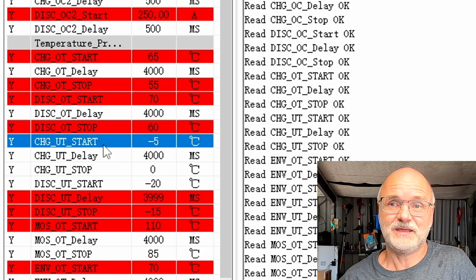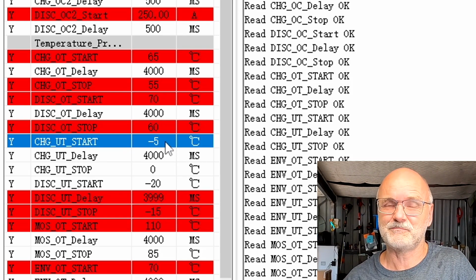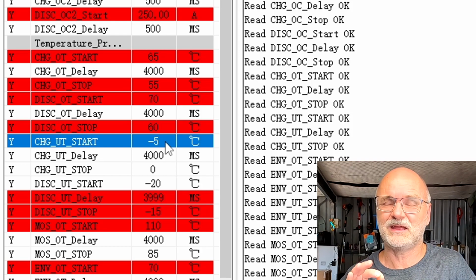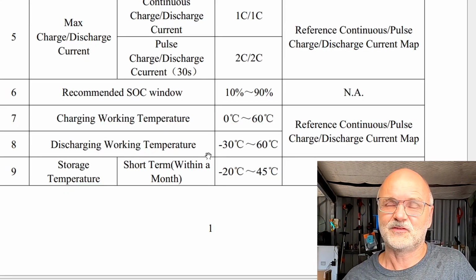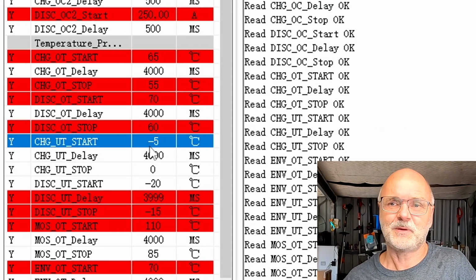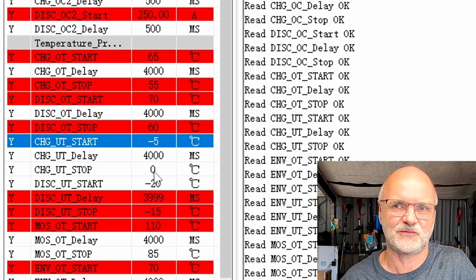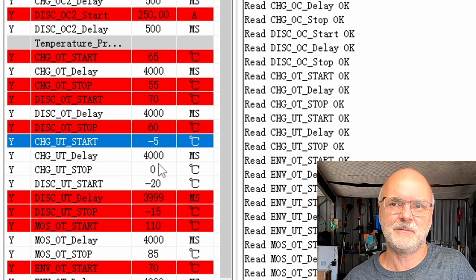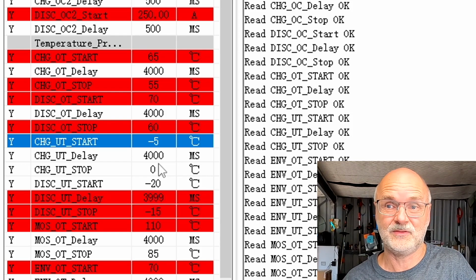And then we come to the charge under temperature start. This kicks in at -5 degrees Celsius. So at -5 degrees Celsius, we can still charge the battery. Looking at the specifications, definitely not. At 0 degrees, we should cut off. So this parameter should not be at -5, it should be at +5 degrees. And the charge under temperature recovery should be at about 10 degrees or so. So again, a wrong parameter here, what is programmed in the BMS.